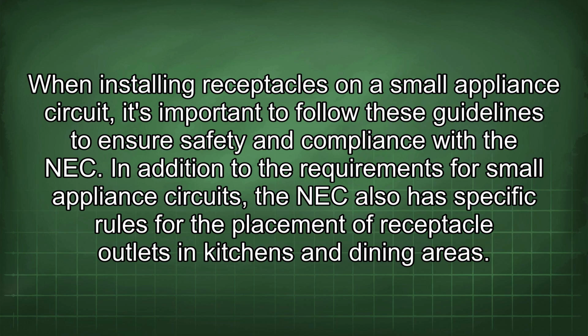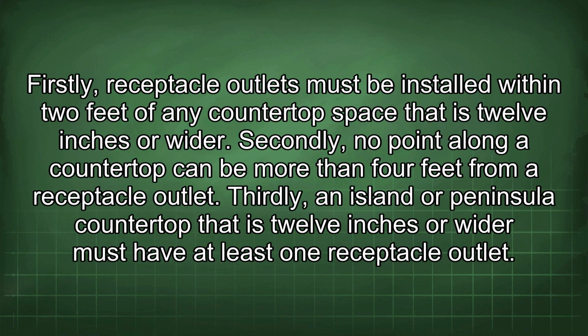In addition to the requirements for small appliance circuits, the NEC also has specific rules for the placement of receptacle outlets in kitchens and dining areas. Firstly, receptacle outlets must be installed within 2 feet of any countertop space that is 12 inches or wider. Secondly, no point along a countertop can be more than 4 feet from a receptacle outlet.